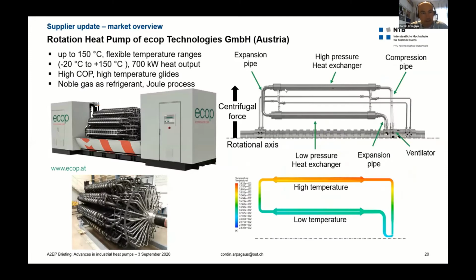I also want to emphasize some other systems not shown before, but they have come up recently. For example, the rotational heat pump from ECOP. It's a company in Austria. This is a different process. It's using the Joule process. There's a gas in these tubes, and these are circulating, so rotating, and the centrifugal force forces the gas to the outside to a higher pressure. Here we have a high temperature, the heat transfer there, and then it goes back into the center.